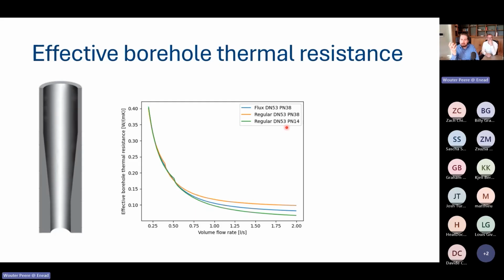And then we lastly have the borehole resistance. So a measurement for how good the borehole or the pipe can exchange energy with the ground. We have again the three cases, and we see here in the beginning everything is laminar, so everything is really close together. We see here a certain bend in the curve. That's where our regular PN38 probe gets turbulence, so it goes down a little bit. So it's the best here, but it's negligible, let's say. Somewhere in between, our flux probe also gets turbulence, and then our theoretical PN14 also becomes turbulent.